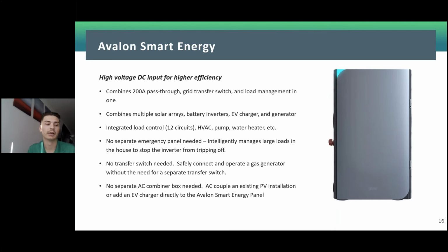Because of the load management, you give the power back to your customer to choose how they want to use it. We'll go through a demo of the app, I believe on the next slide. You'll be able to show them what circuits they want to hot splice from the main service panel or existing critical load panel and put onto the 50 amp relays on the smart energy panel. There's no external emergency panel needed, no transfer switch needed since it acts as that transfer switch, and no AC combiner. You can AC couple or add an EV charger directly into the smart energy panel through the relays on the left-hand side. I'll show you a picture of it with the box open.